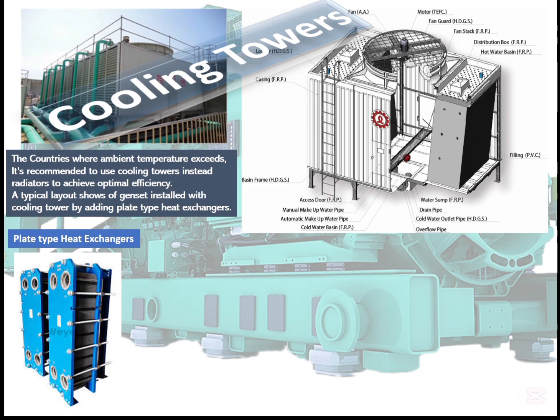In this cooling tower, we are using fresh water with some chemicals. But inside the radiator, we are not using water; the coolant goes from the genset to the radiator and back, so that is a closed circuit. The cooling tower does not work that way. We run fresh water inside the cooling tower, and we use heat exchangers, plate type heat exchangers. This heat exchanger is installed close to the engine. It has an in and out for coolant and an in and out for water coming from the cooling tower. On one in and out, we connect our coolant lines from the engine, and on the other in and out, we install the two lines coming from the cooling tower. When the cold water touches the hot coolant across the plates, the heat dissipates. That's how it works.